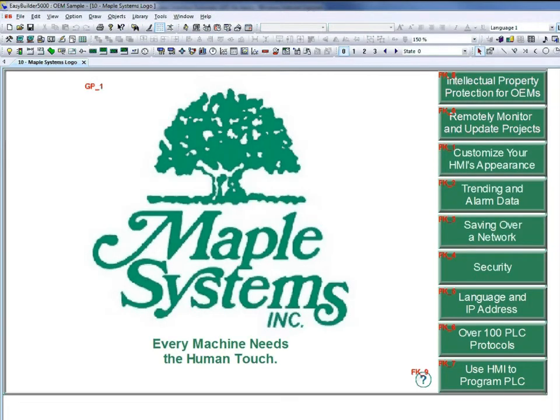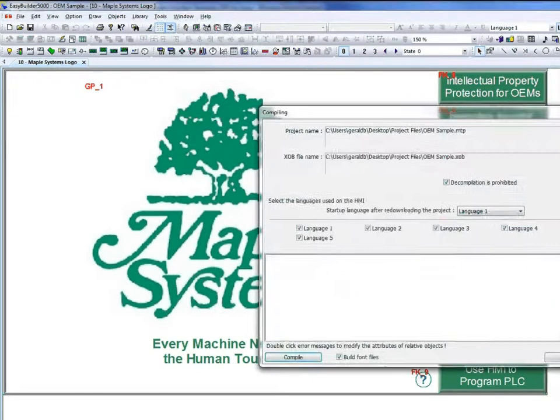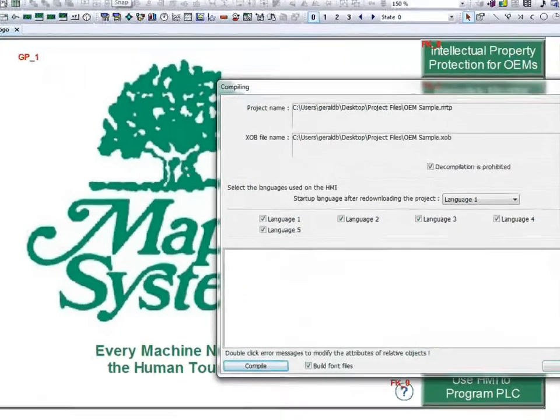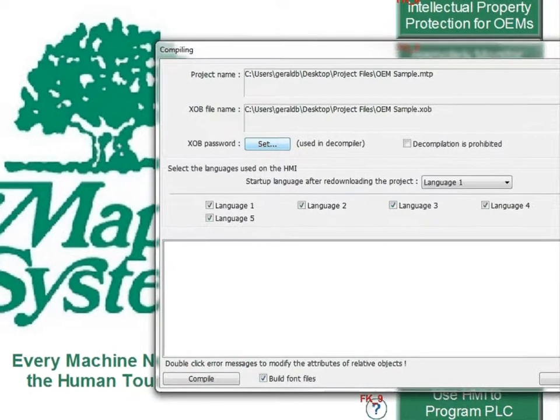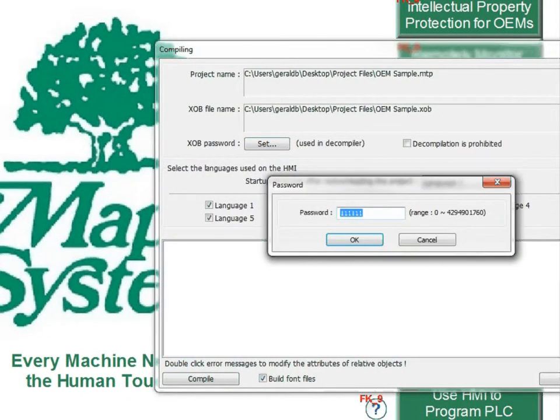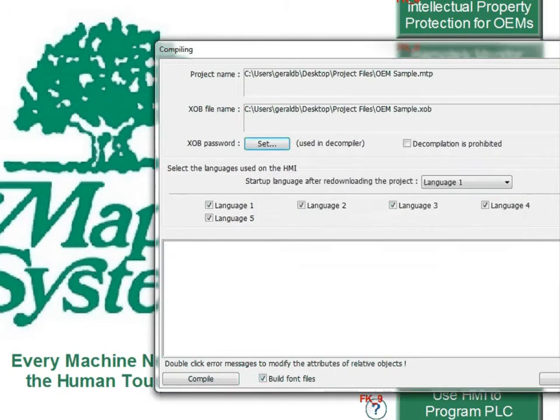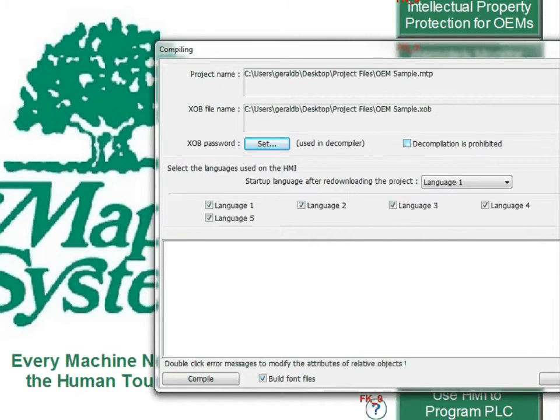Another way to protect your project is to restrict unauthorized decompiling. This is done in the compile window. If you click the set button next to XOB password, you can set a password that the project will need before decompiling. You can also prohibit decompiling altogether by checking the decompilation is prohibited checkbox.